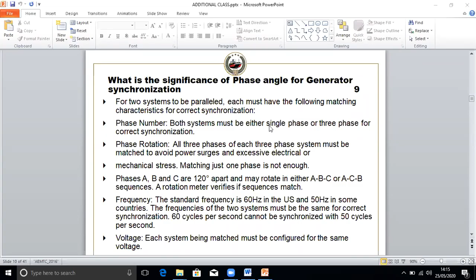Now you look at this, you can see the difference. Phase angle matching requires that waveforms rise and fall together with no angle difference. Now here you see ABC, and here you can see ACB. This phase sequence is not correct. In this example, only the phases are matched, which could cause voltage between the systems to reach twice their peak operating capacity. One system could dead short.